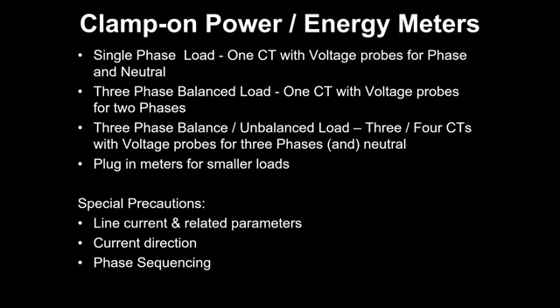So life becomes slightly simplified, because if you have to carry and use a three-phase unbalanced load meter, installation and connection take much more time. It's not just that you have to connect three CTs, you have to connect three voltage probes. Sometimes there are four CTs. So it would take almost 3 to 4 times the time. So normally for motors, we use a three-phase balance load meter, and this is available from anywhere from 7,000 rupees to 50,000 or 60,000 rupees. So depending on your requirement and application, you can select what kind of meter you need.